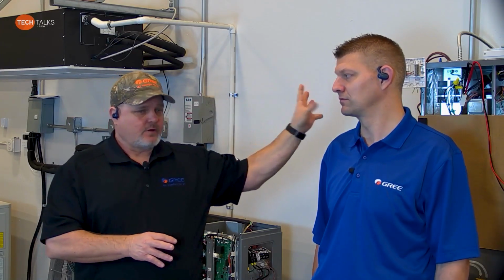The disadvantage, and some people, I don't want to say disadvantage, some people would view it as a disadvantage. If you want Wi-Fi, you're going to have to use GREE's Wi-Fi if you're using GREE's controller. It is Wi-Fi capable. You've got to use GREE's Wi-Fi. Some people like it, some people don't. Again, when I say advantages and disadvantages, it's how the homeowner or end user views them, because I guess you could use this equipment in commercial installations as well. Right. So some people are like, oh no, I've got to have my Ecobee because I really like their Wi-Fi. Well, that's great, okay? So that's the beauty of the system. You can use both. You can do 24 volt or you can use the GREE controller. So you've got options. I like the fact that you've got options.